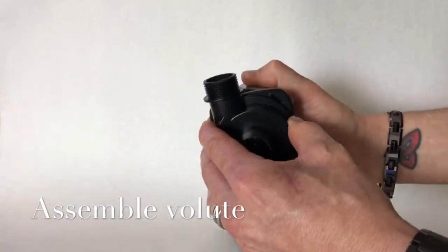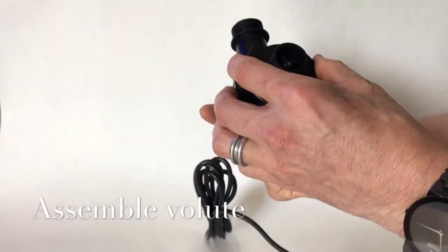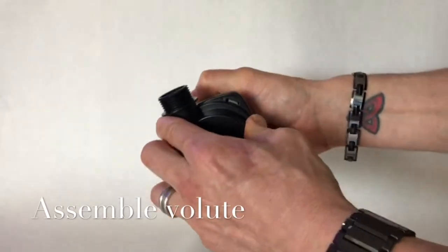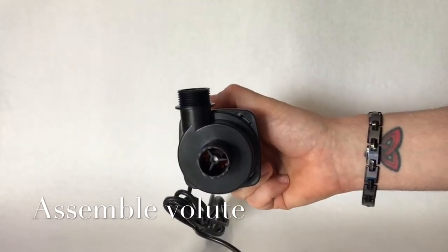When installing the volute on the front of the pump, be gentle when lining up the ceramic shaft with the bushing inside the volute. Once aligned, press them tightly together and give it a turn to install.